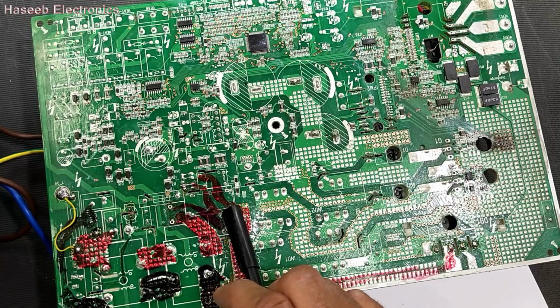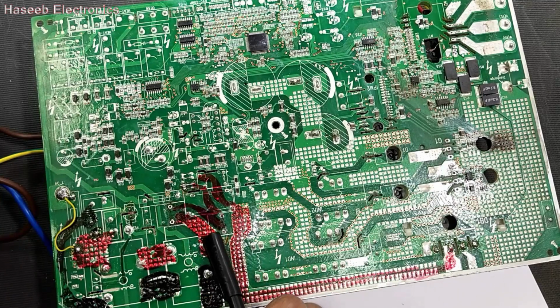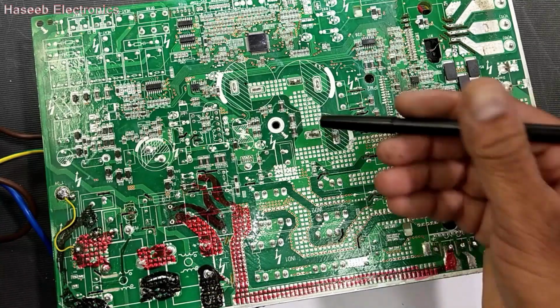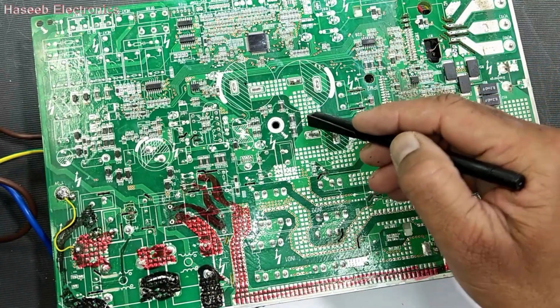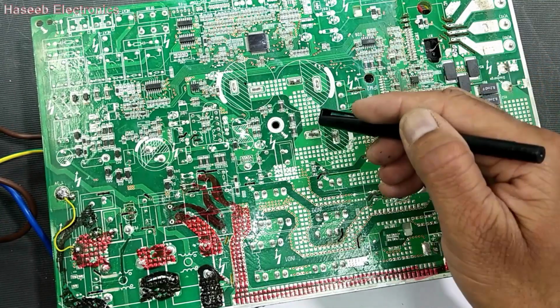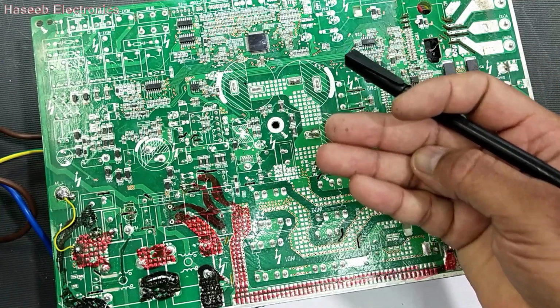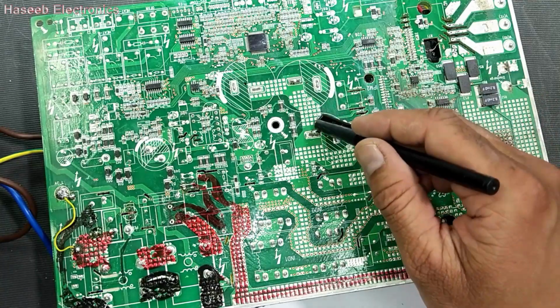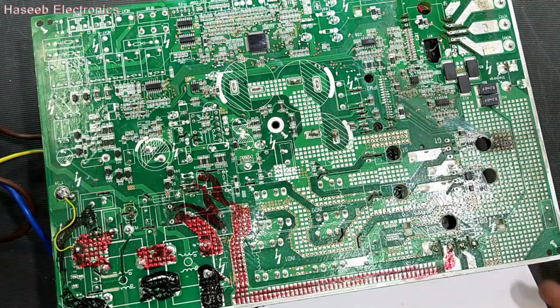When our second relay K2 turns on, the line voltage is directed directly to the bridge rectifier, so it allows the capacitors to charge linearly. This protects against a surge.